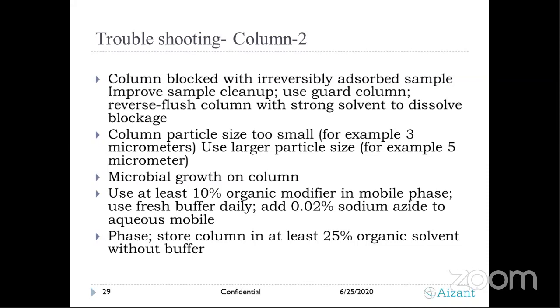Coming to microbial growth, this is a specific challenge when we are using an ammoniacal buffer or a buffer at a higher pH. You'll find after one or two days that your mobile phase seems to be hazy. These observations are very crucial. If you are using a higher pH or a buffer with higher pKa, we recommend that we should not use such mobile phase for more than 24 hours, and we should establish mobile phase stability. Beyond 24 hours we should not use it. Better to use a new one.